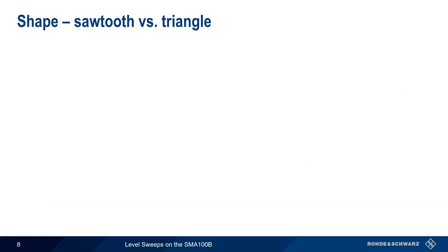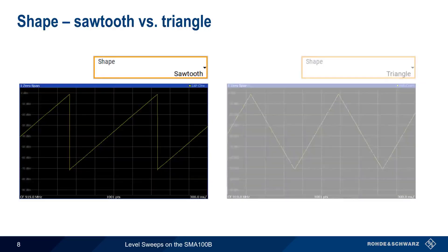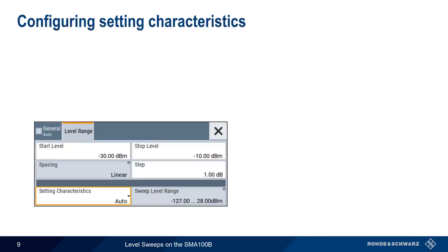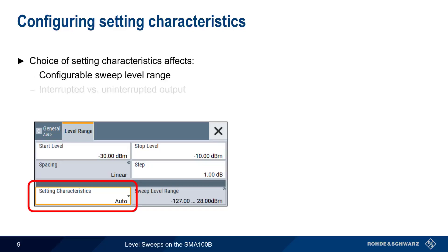In the General Settings menu, we can also choose the shape of the level ramp, either a sawtooth pattern or a triangular pattern. The biggest difference between them being the way they return to the initial output level. The level range menu is where we configure the so-called setting characteristics. The choice of setting characteristics has a significant impact on the configurable sweep level range, as well as whether sweeps are interrupted or non-interrupted.